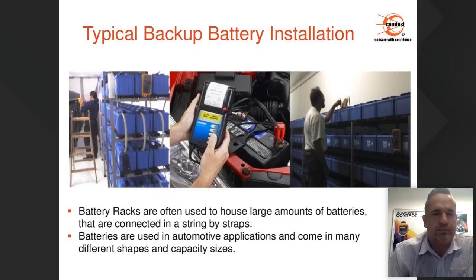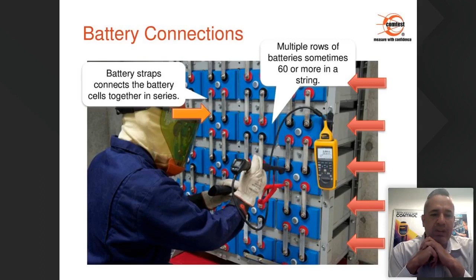The next image refers to a typical battery installation and what we could see there. You can have multiple rows of batteries, sometimes 60 or more batteries in a string. Those batteries will then be connected by links or straps, depending on what you want to call them, and they will join these batteries in a series configuration to give you higher DC output voltages. When batteries are connected in this configuration, you can see there's a large amount of batteries and the risks are potential, so always adhere to safety standards, wearing the correct PPE when testing batteries.